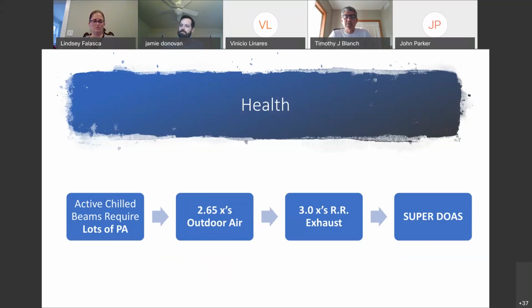And so what did this lead to? What I call super DOAS. A lot of people do DOAS, dedicated outdoor air system, and that's what we have here. But nobody does a super DOAS where all of the air to the terminal devices, whether they're VAVs or chilled beams, is outdoor air. So that was a big difference here. So we have very large DOAS units for this building. But that's basically the process.